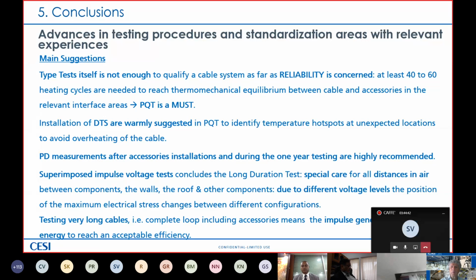Superimposed voltage test concludes the long duration test for DC cable system only. A special care for all distances in air between components, the walls, the roof, and other components has to be taken. Due to different voltage levels, the position of maximum electrical stress changes between different configurations. As I said, it's not like the HVAC when you have only one lightning impulse, 10 plus, 10 minus, finish. In this case, we have different polarity, different voltage levels, so the distances, the clearances in air between components, walls, roof, and other components is very, very much of importance.